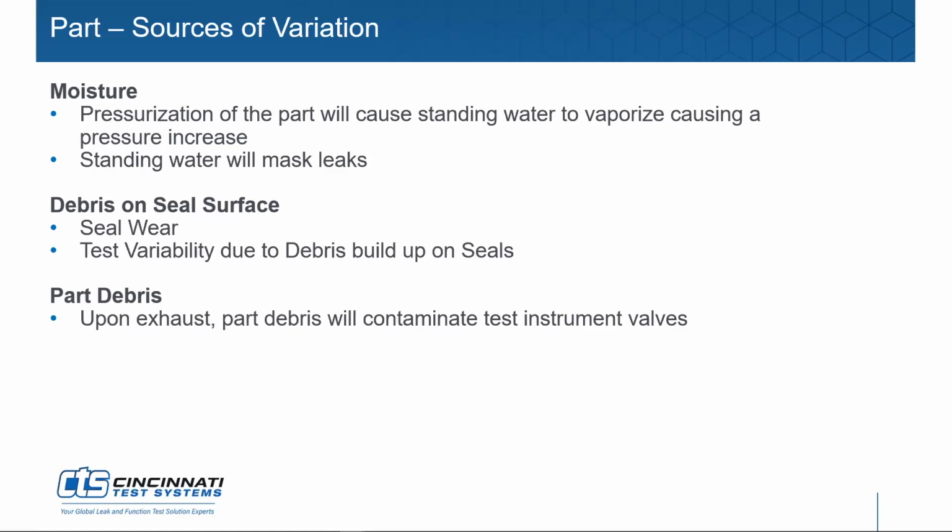The other thing that happens when you compress gas into a part that has standing water is it atomizes the air. And what happens with humidity is it actually causes lower air density. Lower air density gives a measurement of pressure loss that is less compared to higher density air. So now we're getting into some physics associated with air density. Like, oh my gosh, why is this going to be that complicated for you?